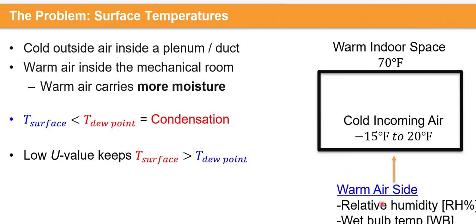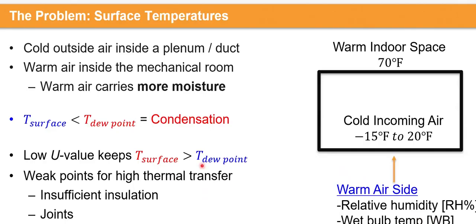To specify this, we need to know what the relative humidity would be in the space. We need to know either the wet bulb temperature or the dry bulb temperature to fully specify this. The temperature at the surface would also be impacted if you have insufficient thermal transfer, right? So if you have a high thermal transfer right at your joints, or you do not have enough packing of the insulation in the panels, you would have a lower temperature at those locations. And if you have some air leakage as well, that would also lead to a much lower surface temperature that would eventually lead to condensation.